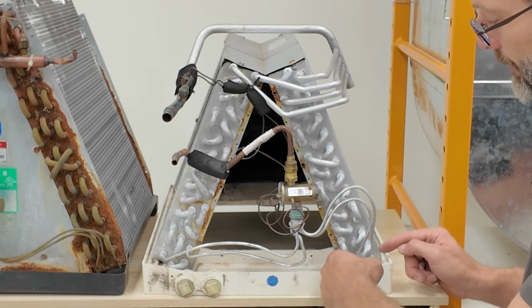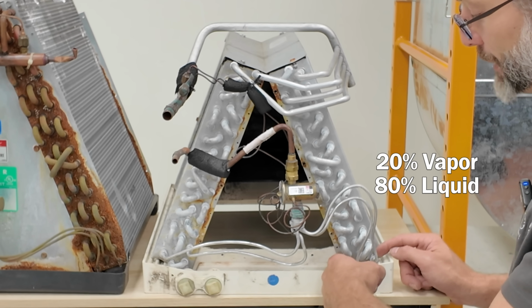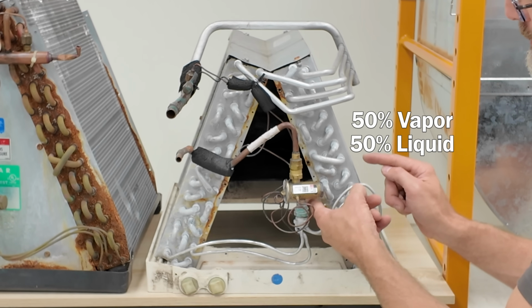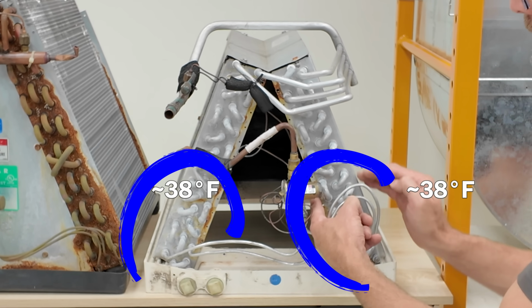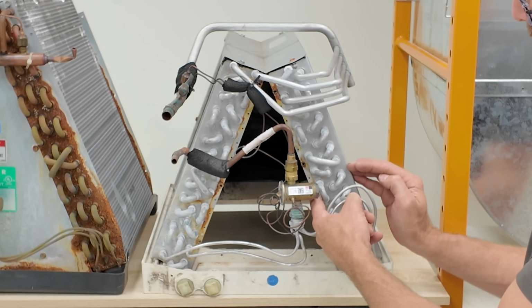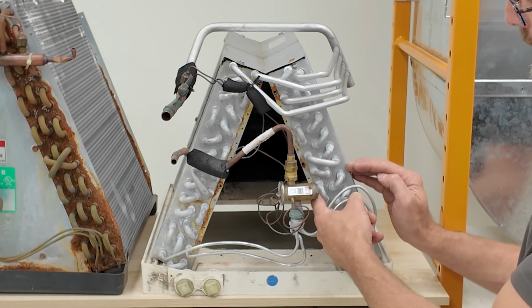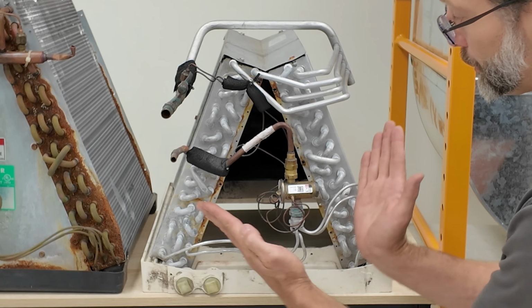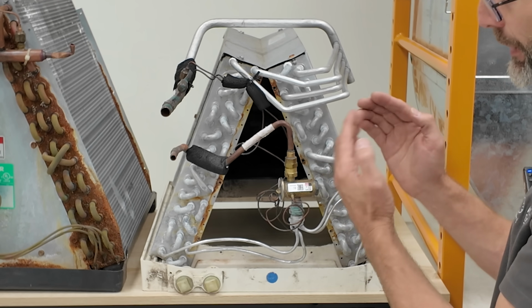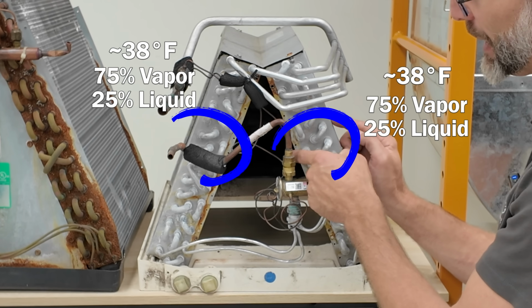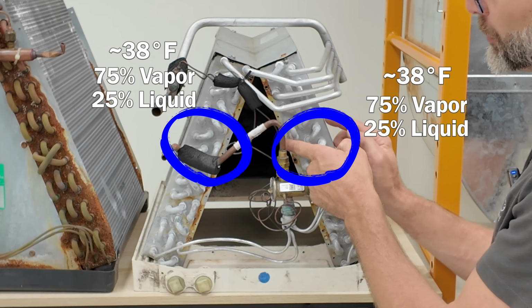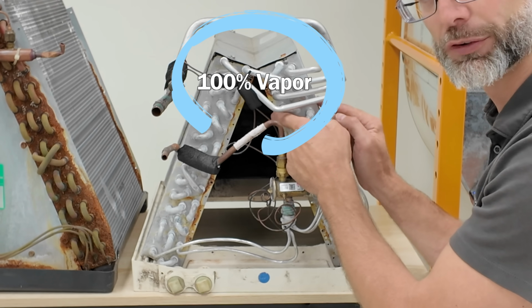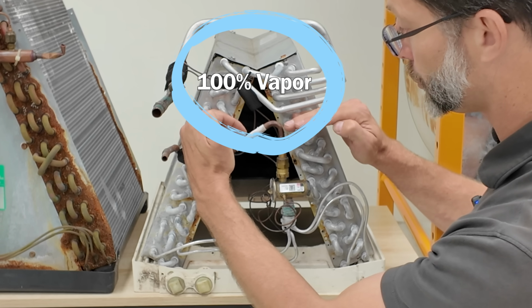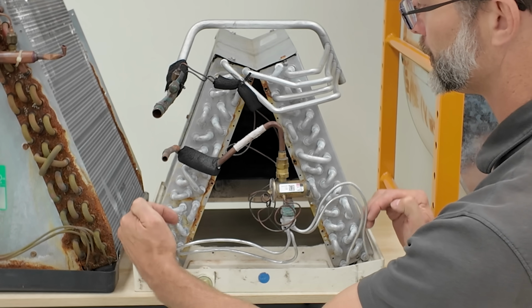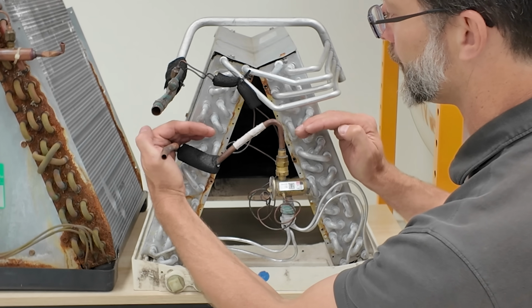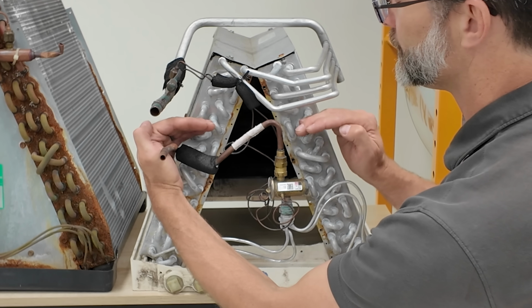And so you have, say, 80% liquid, 20% vapor here, then maybe a 50-50 mix. So this would all be, say, 38 degrees. And as you have air traveling through this coil, you're going to have a phase change occurring. Then you're going to have, say, 75% vapor, 25% liquid, and then you're going to be fully in the vapor state by the time you get up to here on this coil. So the phase change is occurring from here up to here on both sides, and then it's completely in the vapor state.